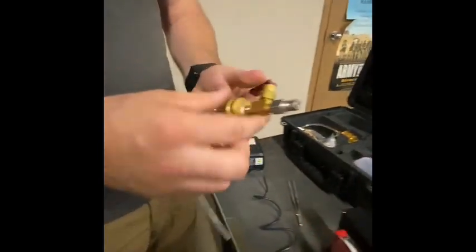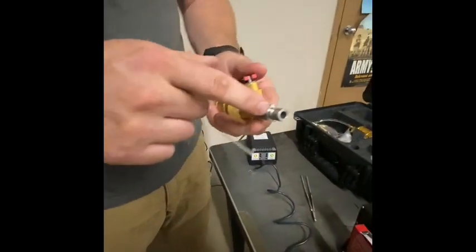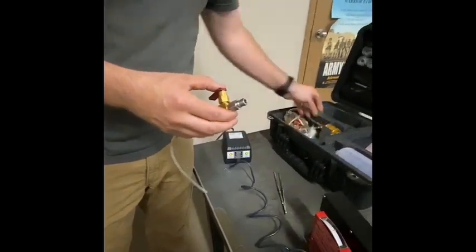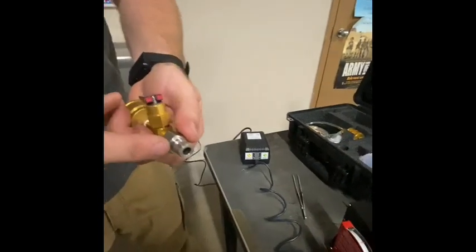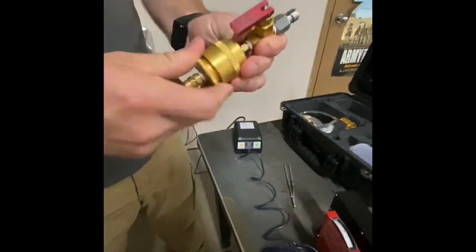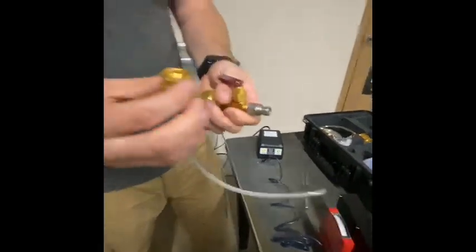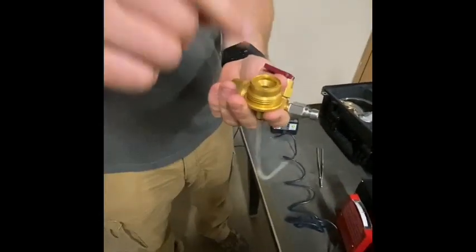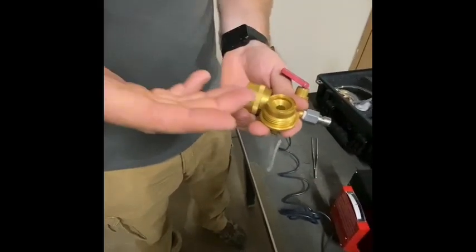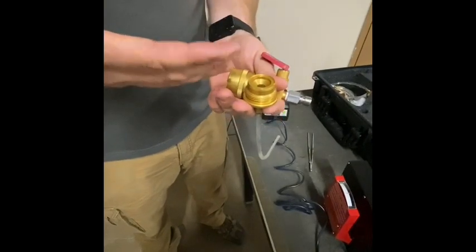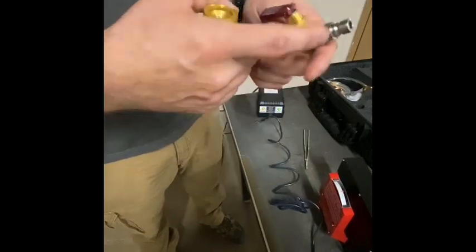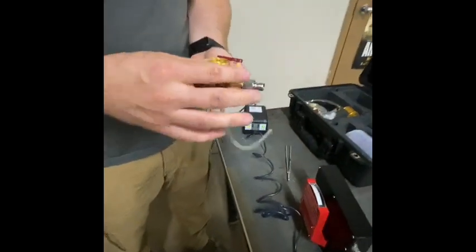Now, if you remember, I mentioned the fuel testing port. Same fuel testing port is used for both of these test systems. You put it into the fuel testing port, and you would have this pad. You put the pad in this side right here. Now, the saying is sunny side up. So what you do is when you put the pad in here, it is yellow facing up. The yellow is facing the inlet side of your testing device.